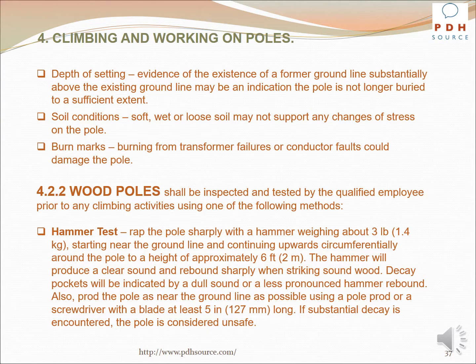Depth of setting: evidence of the existence of a former ground line substantially above the existing ground line may be an indication the pole is no longer buried to a sufficient extent. Soil conditions: soft, wet, or loose soil may not support any changes of stress on the pole. Burn marks: burning from transformer failures or conductor faults could damage the pole.